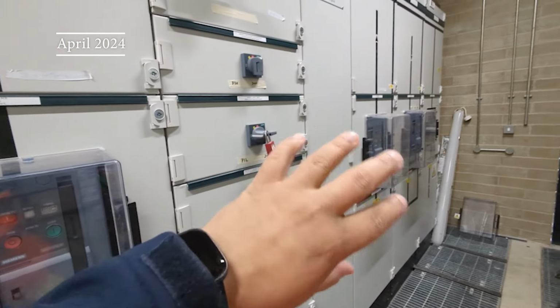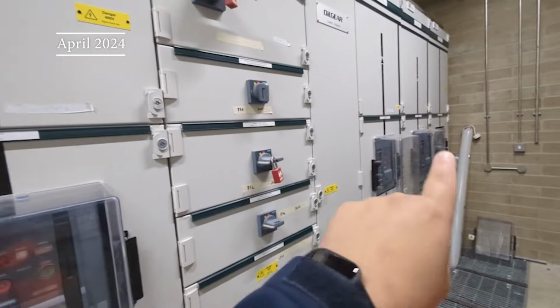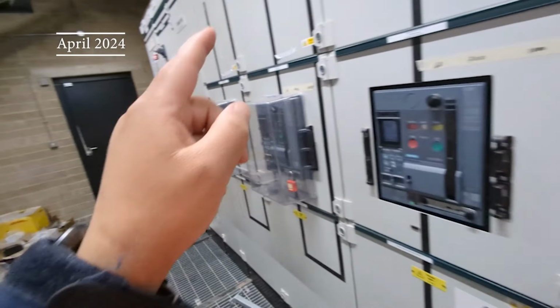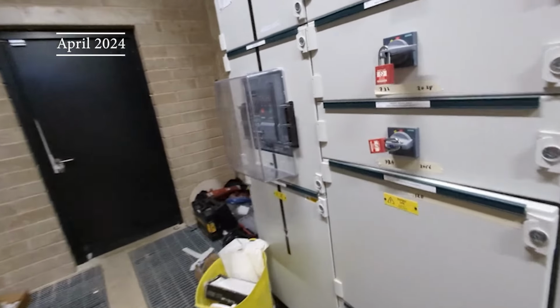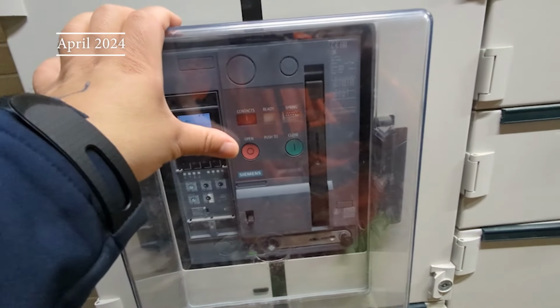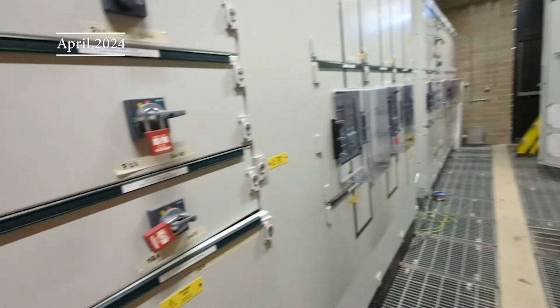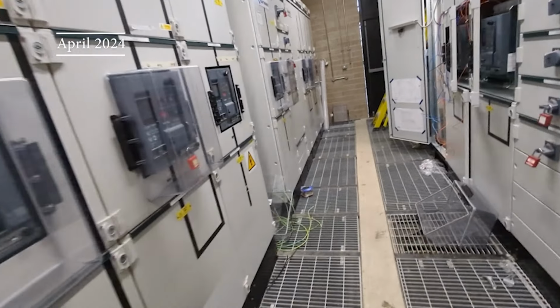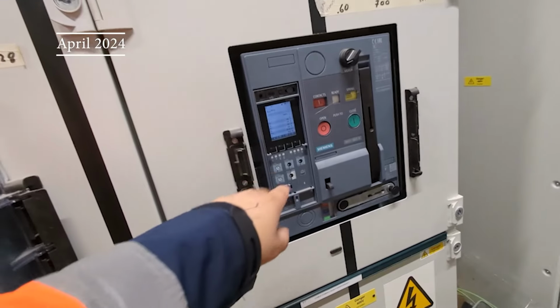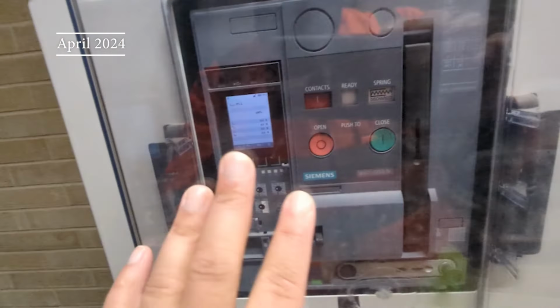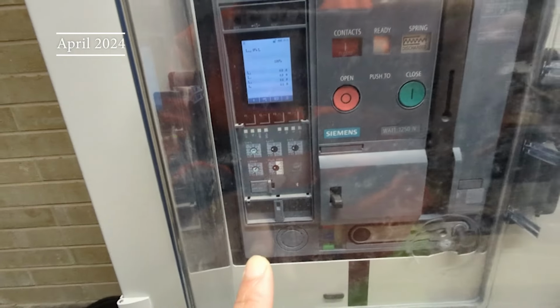So all of this is duplicated, right? You've got one transformer feeding this ACB, which feeds the hydraulics next door, and then you've got a different transformer feeding this ACB. This ACB then feeds this 1200 amp one, and again, this isn't blowing. So I need to adjust the settings on the main incoming ACBs, these. I also need to adjust the settings on this ACB, because it should be blowing at 1100 amps, and it's not.